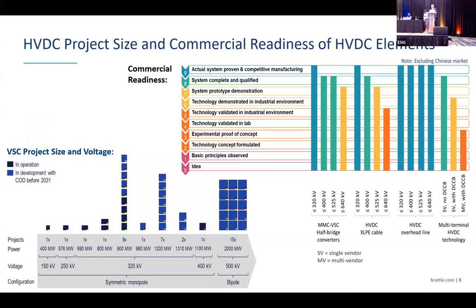Well, we are quickly running out of time, so we'll have to skip ahead a little bit, but this slide shows you what is already in operation versus what is prototype, what is fully qualified versus what's coming in. You see in the lower left corner the kind of transfer capabilities and voltages that VSC converters are already operating at. The dark boxes and the light blue boxes are all the projects that are already planned. And what you can see on the right is that a 2 gigawatt, 525 kV technology setting is quickly becoming the standard. What you see on top with the bars is that some of these technologies that are now being planned for deployment are not operating yet. So these are brand new technologies that have been fully tested and qualified, but there is definitely some new technology development going on as we speak.